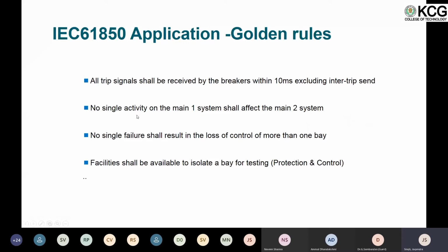There is no single activity on the main one system that should affect the main two system. In an EHV grid, we always have one main one system and one main two system for protection. But for control, we normally have one system only. No single failure shall result in loss of control for more than one bay. So if you have an IED for control, there is only one bay, most probably, that will be out of control if you have a failure in that device. There will be different facilities available to isolate a bay for testing. You have a test switch, so you can put it in test mode and you can test the protection and control.